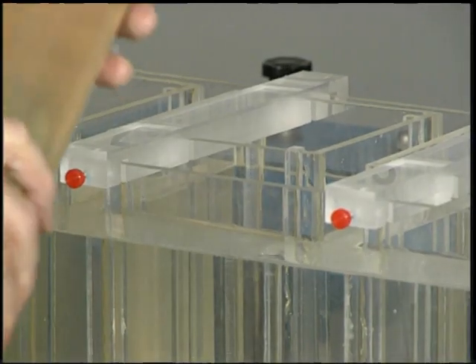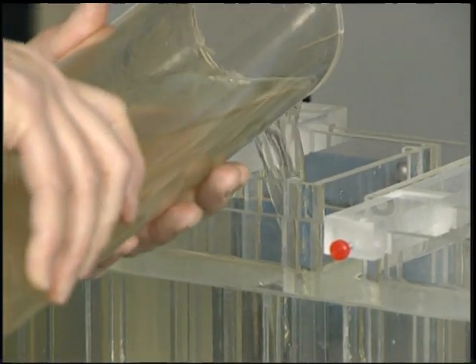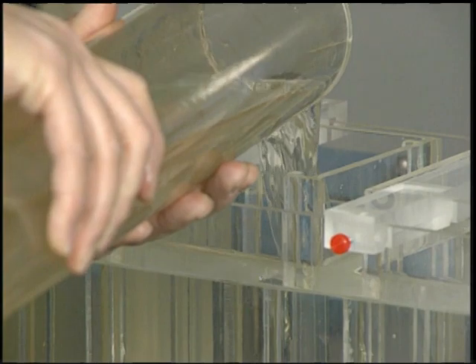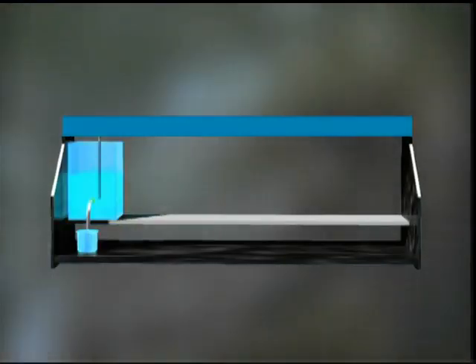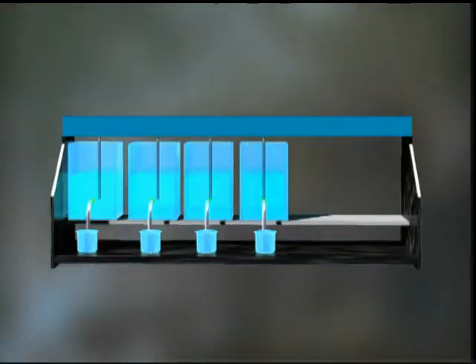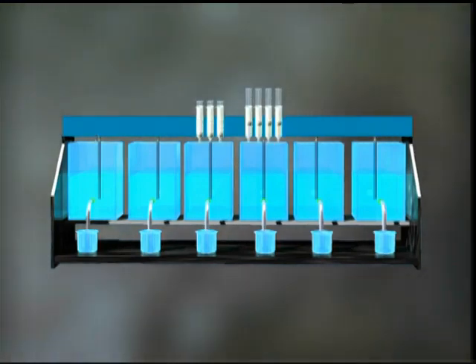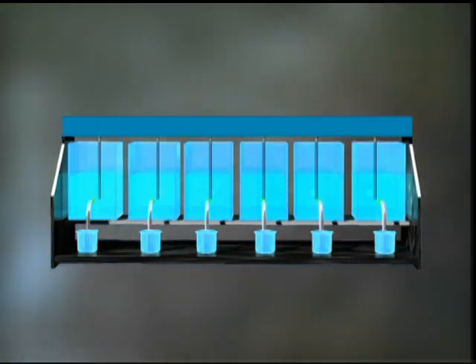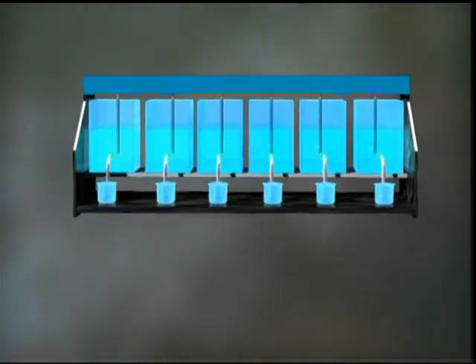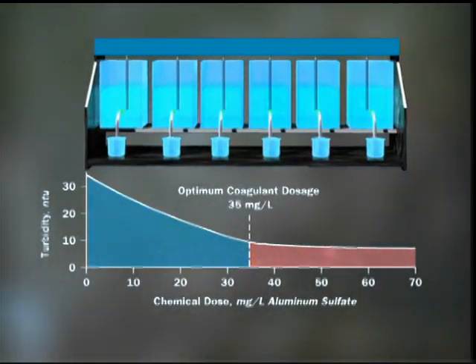By using jar tests, operators are able to experiment with different chemicals and doses. The basic jar test procedure involves collecting a sample of the raw water and adding progressively larger doses of the coagulant chemical to several jars of the sample. The results are used to identify the optimal dose for turbidity removal.